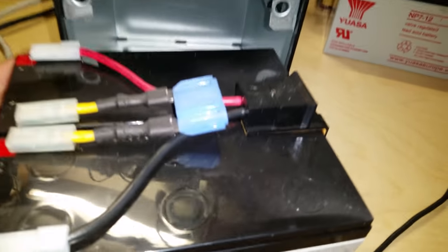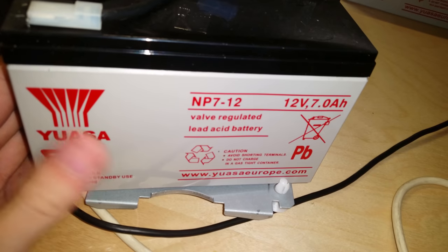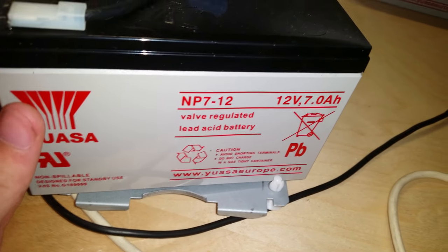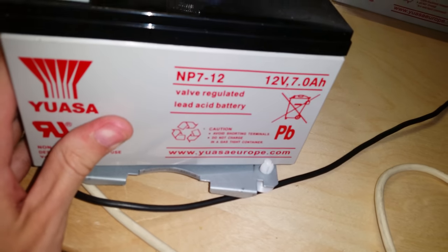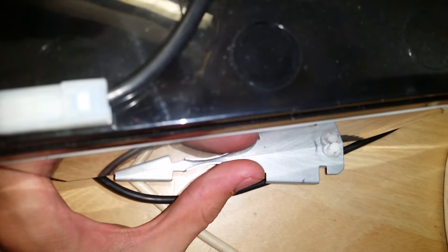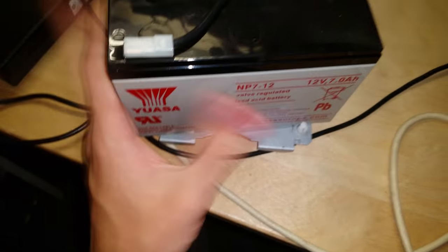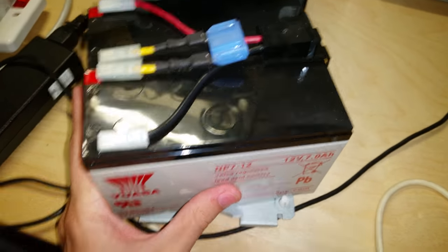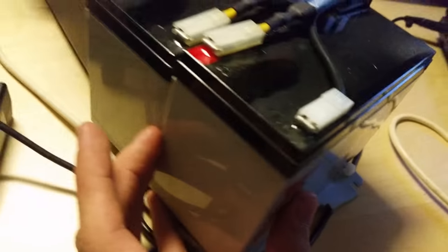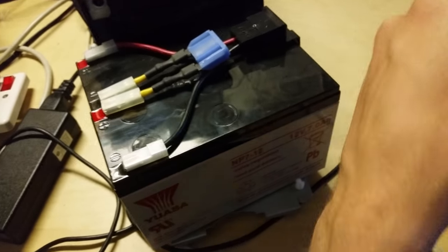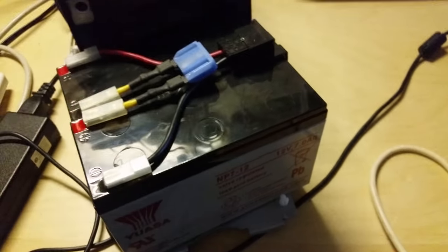Like so. Pull them around. You can see they're the same batteries here as I've now got over there to replace them. There is a slight bit of a bulge on the side of them here, but not very much. This is why I use this brand of batteries, because they don't leak and they don't really cause me any problems. So I need to now get these other batteries and put these connectors and things onto them, and then we can insert them into the unit. I'm going to move this stuff out of the way and rebuild this battery pack.